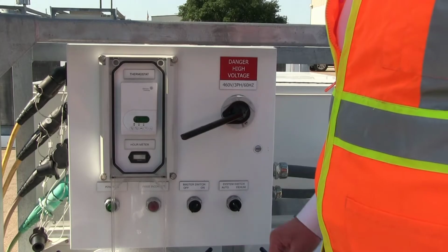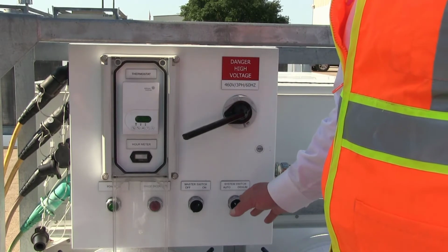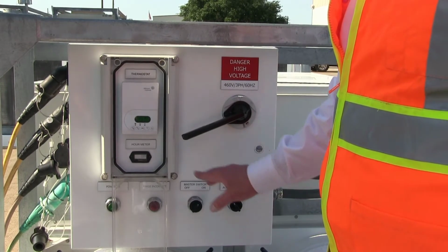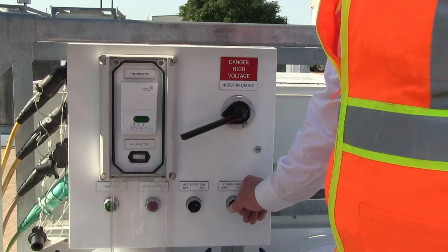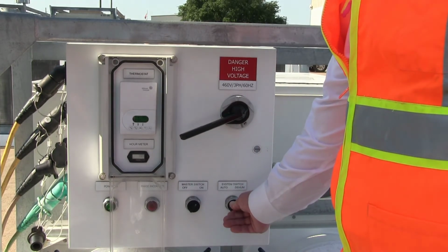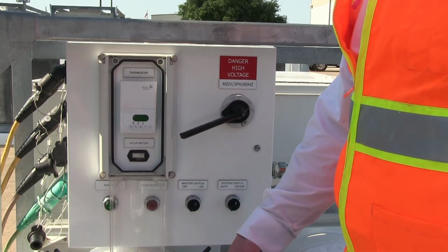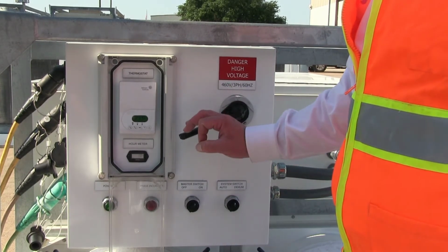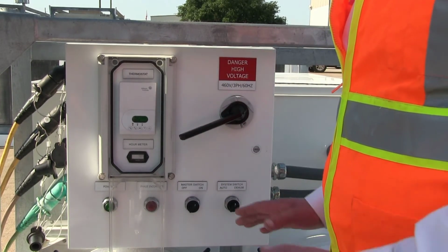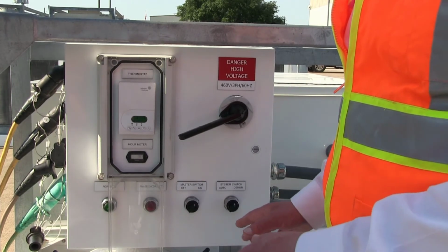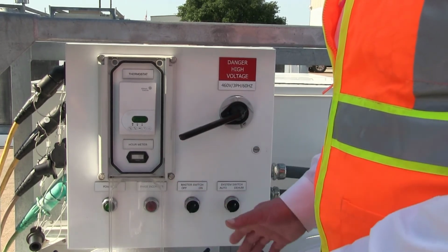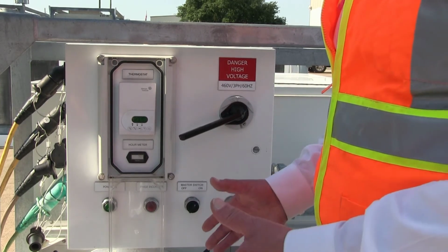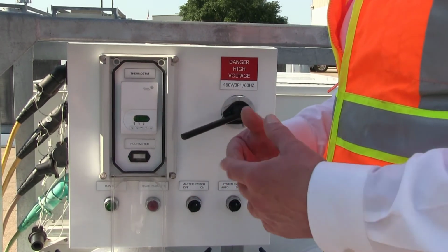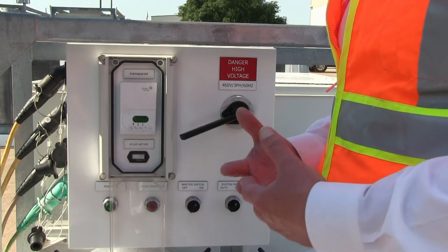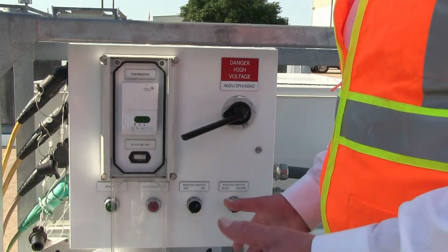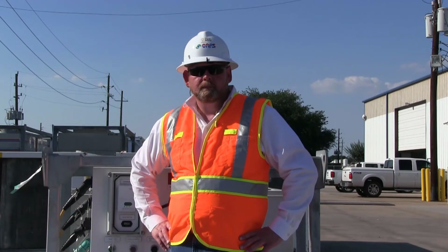Let's talk about the dehumidification, which is our third mode of operation for our 5-ton unit. Right now it's being controlled by the thermostat. By simply going here and turning the switch to dehumidification, it's going to take it the maximum airflow, it's going to run all of the cooling and turn all of the heating on. At this point the machine does nothing but provide cool, dry, neutral air. Its job is just to remove humidity, and we'll typically run this mode during restoration, or if we have a high humid environment that needs dehumidification, we'll use the unit in our DH mode.